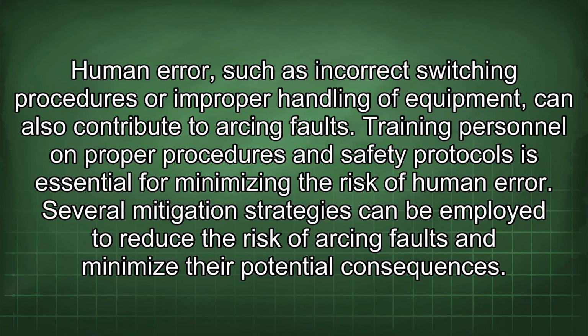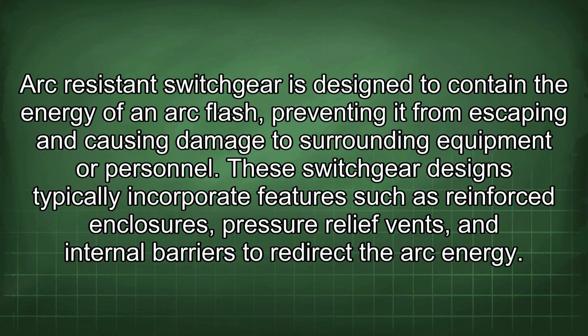Training personnel on proper procedures and safety protocols is essential for minimizing the risk of human error. Several mitigation strategies can be employed to reduce the risk of arcing faults and minimize their potential consequences. Arc-resistant switchgear is designed to contain the energy of an arc flash, preventing it from escaping and causing damage to surrounding equipment or personnel. These switchgear designs typically incorporate features such as reinforced enclosures, pressure relief vents, and internal barriers to redirect the arc energy.